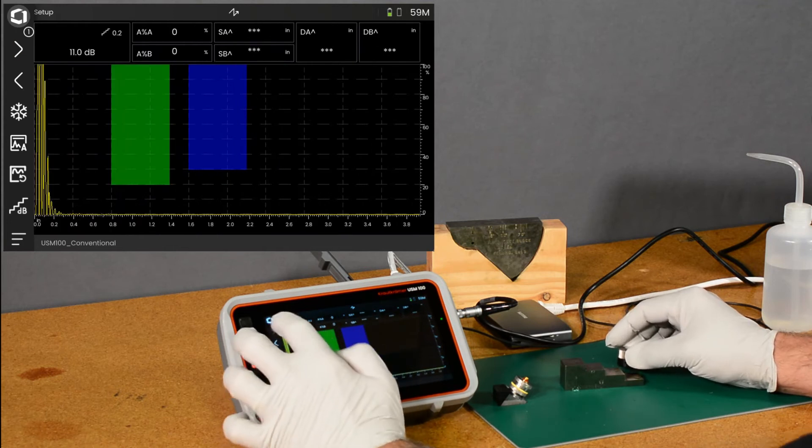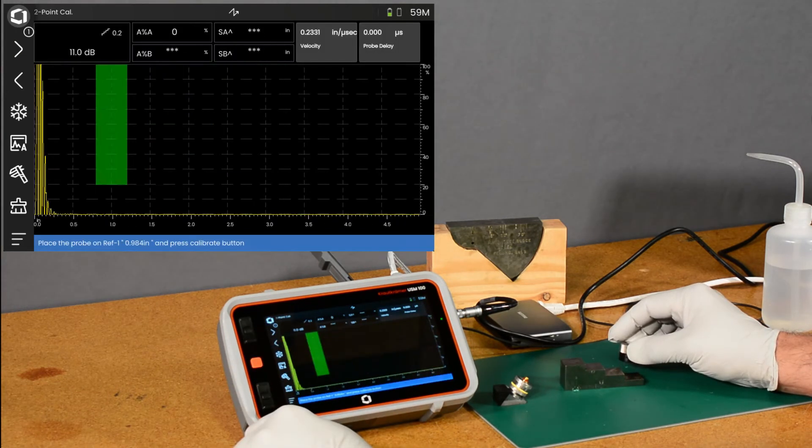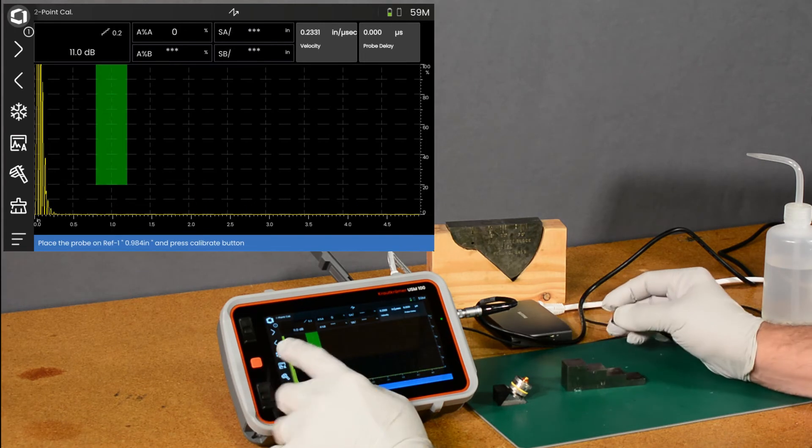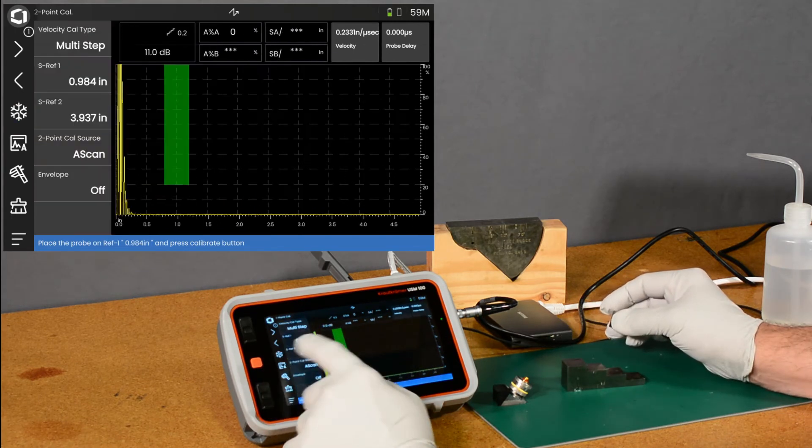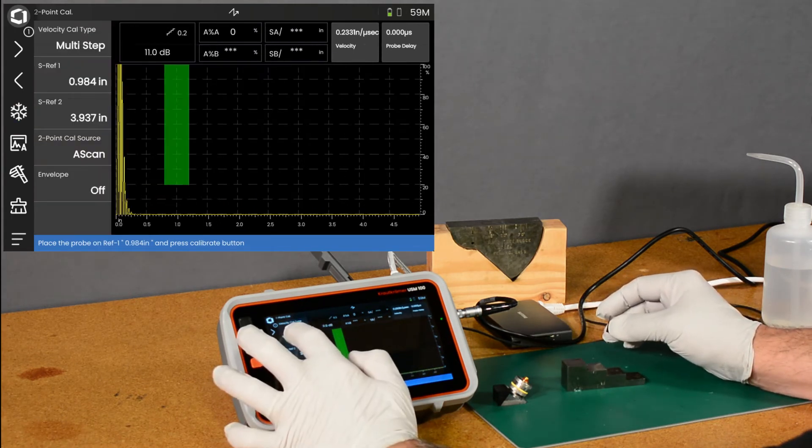and we'll go to our two-point calibration menu. And I'll swipe out my sidebar. I'm going to calibrate on the 1 inch thickness, so we'll change that to an inch.